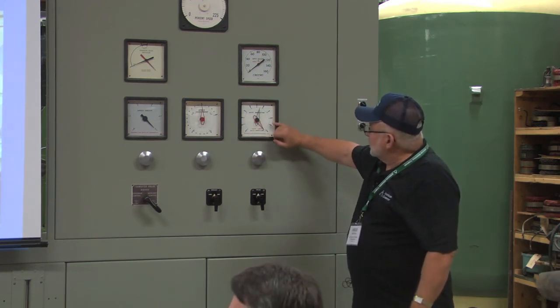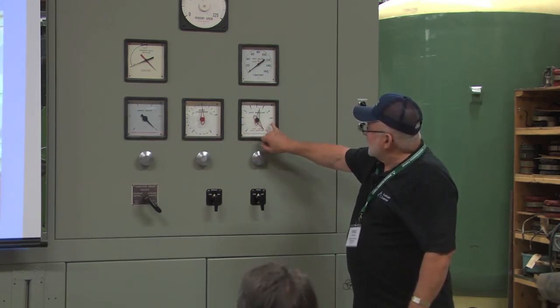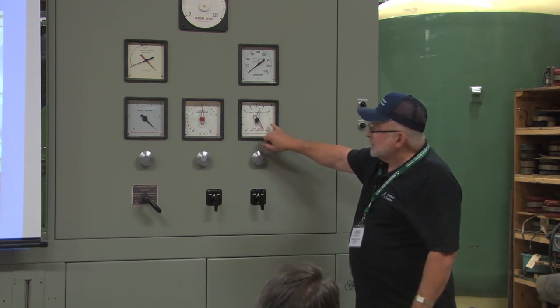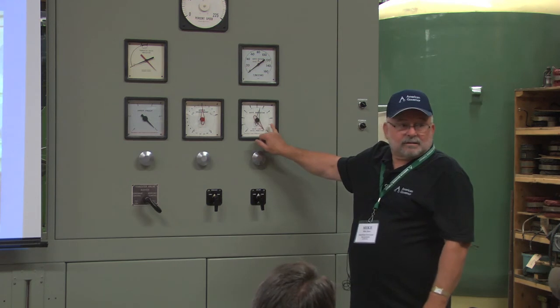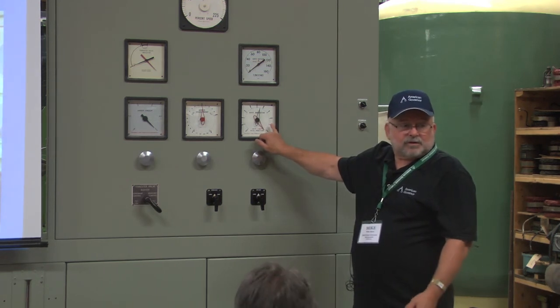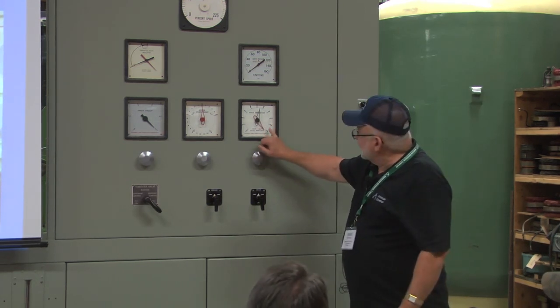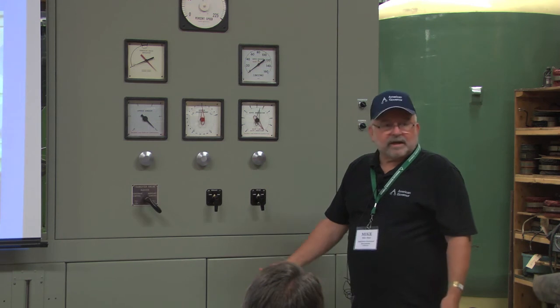First of all, from about 76 to 86 is about as high as you'll ever see on these units at full load, because the rest of this is if you had a real low head. You know, we run about 82. Yeah, and that's full load.